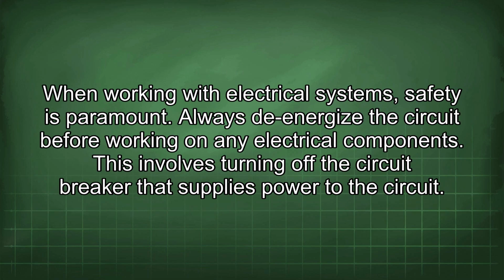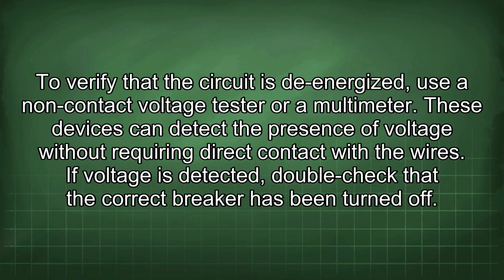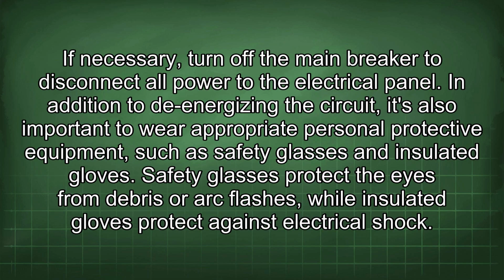When working with electrical systems, safety is paramount. Always de-energize the circuit before working on any electrical components. This involves turning off the circuit breaker that supplies power to the circuit. To verify that the circuit is de-energized, use a non-contact voltage tester or a multimeter. These devices can detect the presence of voltage without requiring direct contact with the wires. If voltage is detected, double-check that the correct breaker has been turned off. If necessary, turn off the main breaker to disconnect all power to the electrical panel.